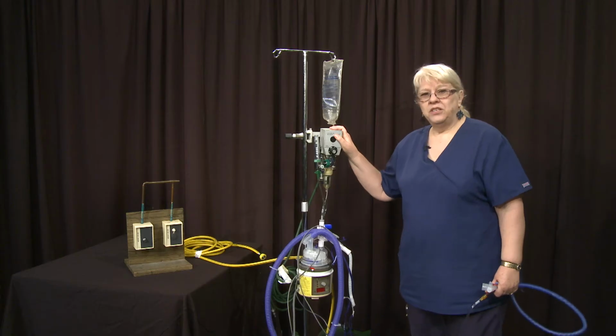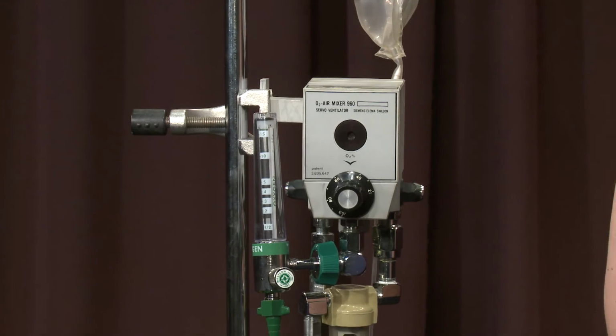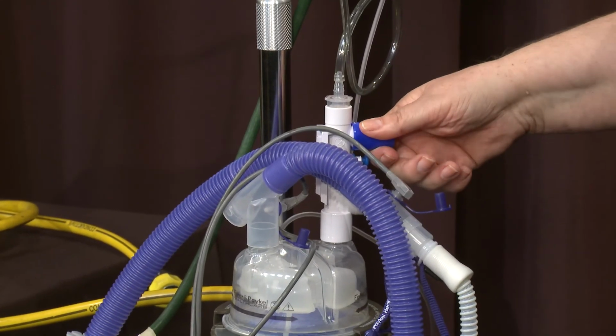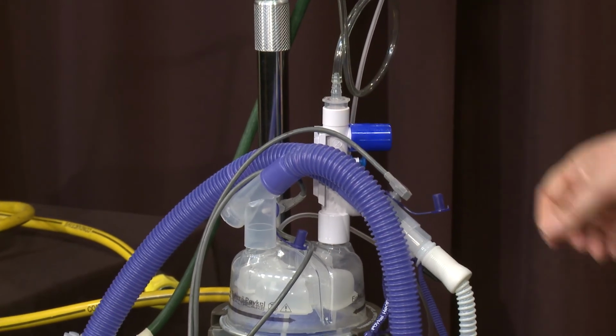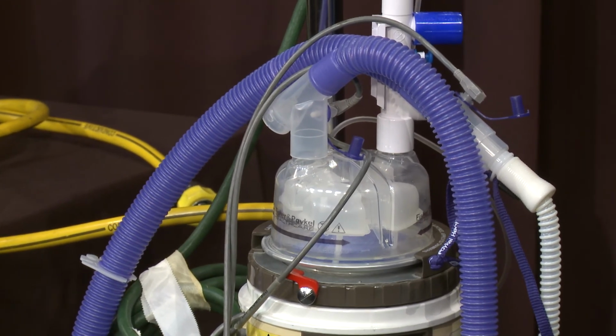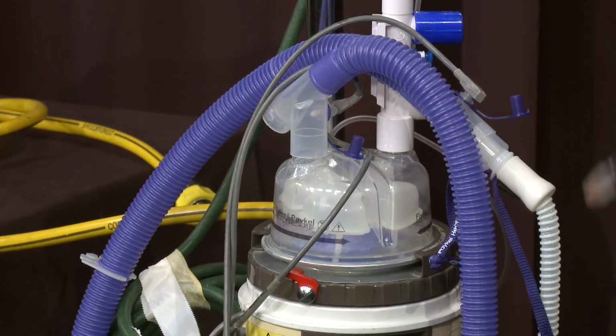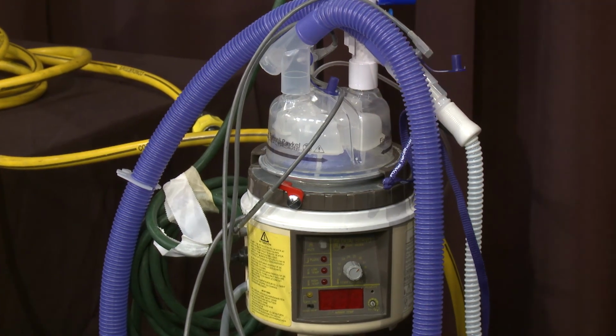Now, just as a quick review, the blender is likely to alarm when there is a greater than 5 psi difference between the air and the oxygen pressure. We know we have a pressure pop-off in the circuit to relieve pressure so it doesn't harm the patient. We know that a modified passover humidifier, which is at body temperature, can't produce aerosol particles. And we know that heating is important because aerosol particles are very likely to pick up bacteria which can be delivered to the patient. We know the heated wires prevent rainout, and we know that the servo control allows us to maintain body temperature.